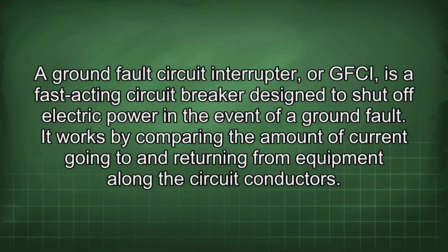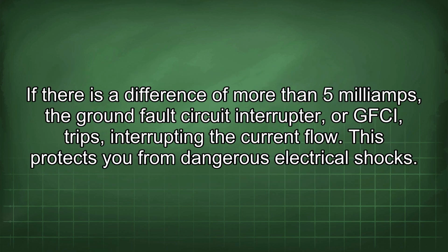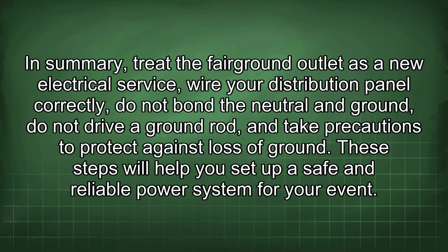It works by comparing the amount of current going to and returning from equipment along the circuit conductors. If there is a difference of more than 5 milliamps, the GFCI trips, interrupting the current flow. This protects you from dangerous electrical shocks. In summary, treat the Fairground outlet as a new electrical service. Wire your distribution panel correctly. Do not bond the neutral and ground. Do not drive a ground rod, and take precautions to protect against loss of ground. These steps will help you set up a safe and reliable power system for your event.